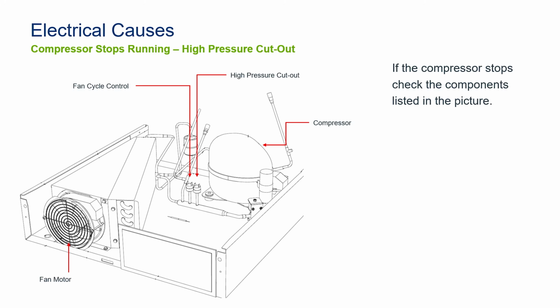But the easiest way to test this that I've found: turn the machine off, pull the wires off the fan cycle switch and jump them to each other. Turn the ice machine back on. You have now created a closed circuit for that. As soon as the contactor pulls in, that fan should run. If it's running, that'll tell you the fan cycle switch failed, because we took it out of the circuit and the fan did its job. If you jump that fan cycle control switch out and the fan still does not run, first thing I'd recommend, check your jump, let's be sure. But if it's a good jump and that fan still will not run, you've given it direct power once that contactor pulls in. You'd be looking at a fan motor problem.